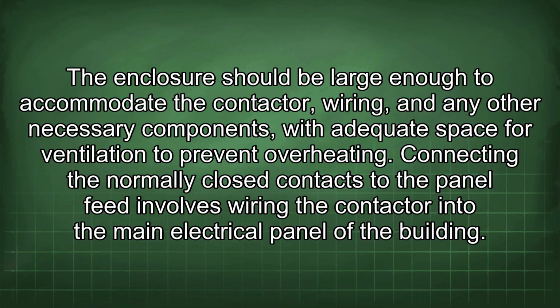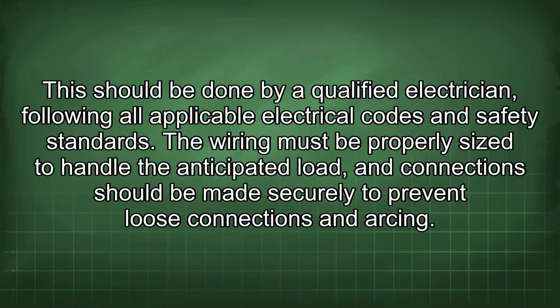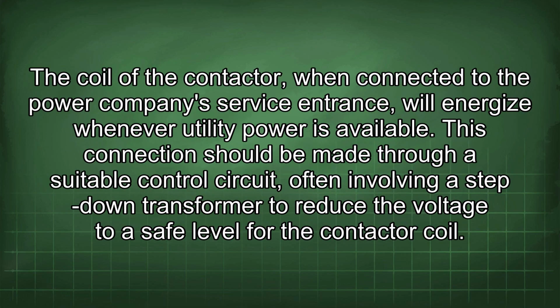ventilation to prevent overheating. Connecting the normally closed contacts to the panel feed involves wiring the contactor into the main electrical panel of the building. This should be done by a qualified electrician, following all applicable electrical codes and safety standards. The wiring must be properly sized to handle the anticipated load, and connections should be made securely to prevent loose connections and arcing. The coil of the contactor, when connected to the power company's service entrance, will energize whenever utility power is available.